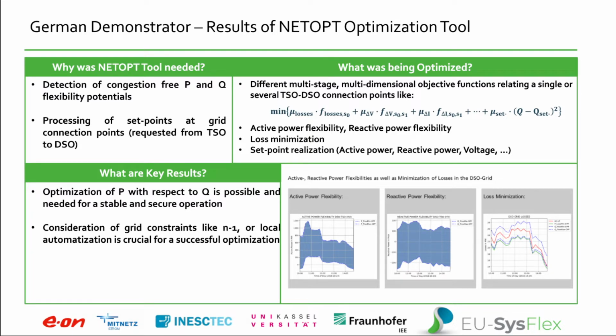You can see here, this is our optimization approach. As I said, this was active power flexibility, reactive power flexibility, and loss minimization, and then set point realization, because when you have a potential at the grid connection point and you have a set point at the grid connection point, you need to deaggregate this set point to the individual power plants.